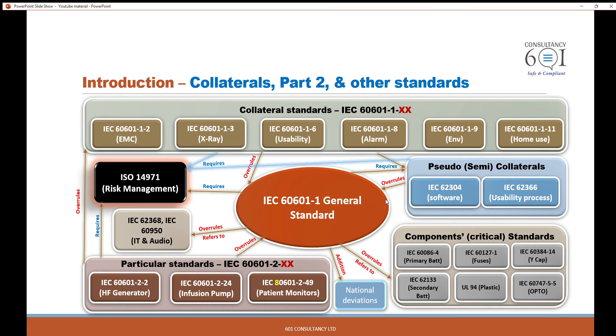The other standards — like pseudo or semi-collateral standards — cover software and usability. So those are the medical standards, all of them. Then there are some non-medical standards, the component standards, which are applicable to the components mentioned. For example, if you have a secondary battery employed in the equipment, you need to meet the requirement of IEC 62133, in addition to the requirements of IEC 60601-1.